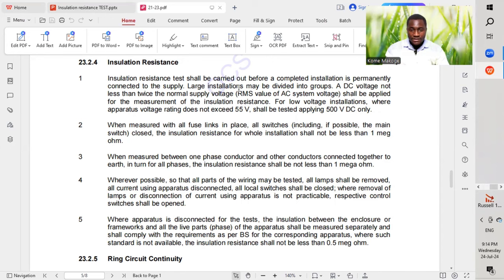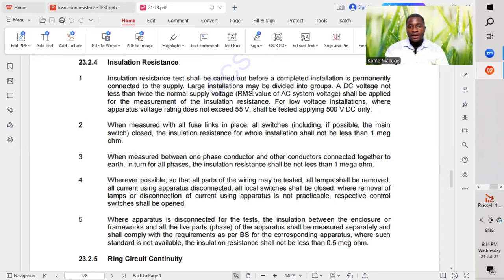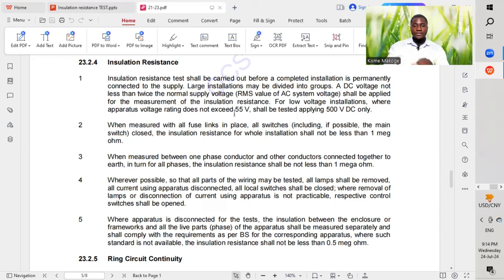Large installations may be divided into groups. The DC voltage, not less than twice the normal supply voltage RMS value of the AC system voltage, shall be applied to the measurement of the insulation resistance. This is very important.